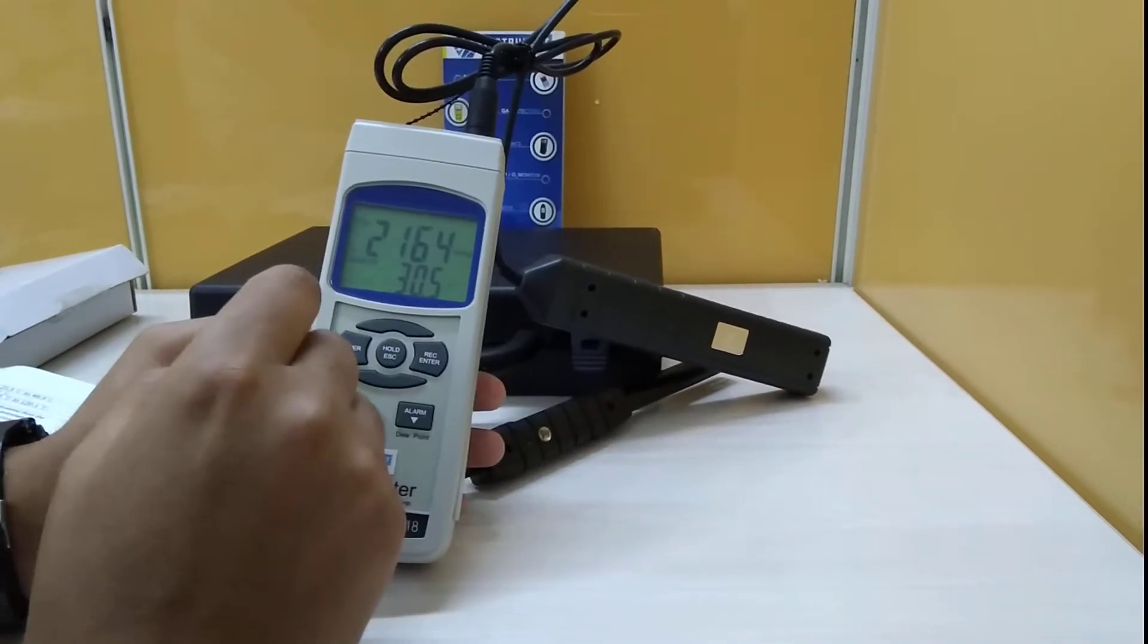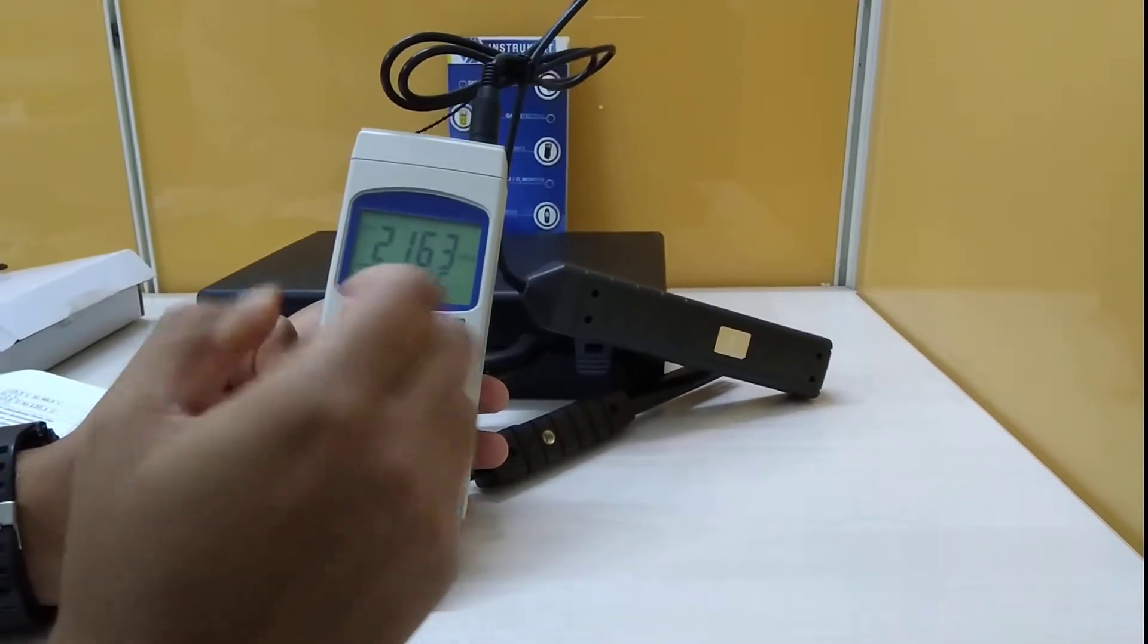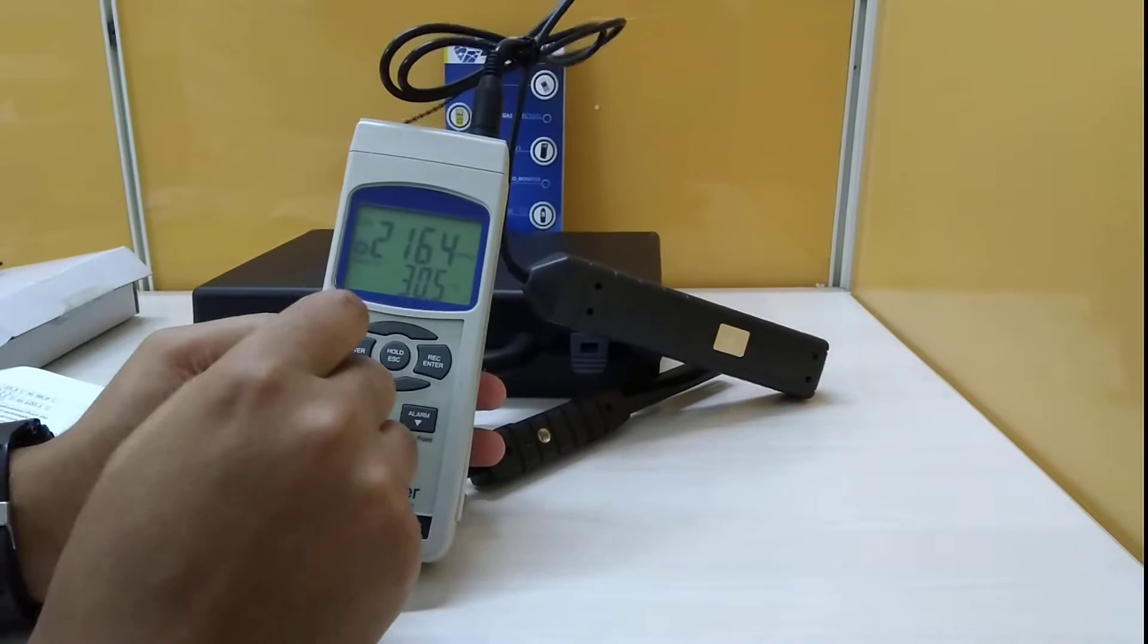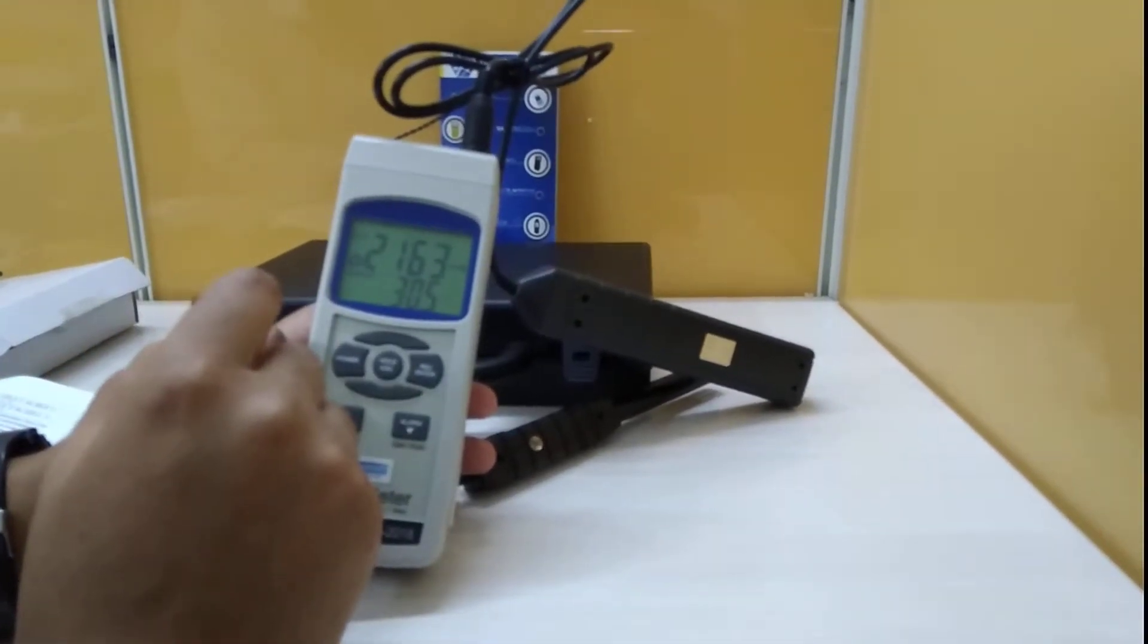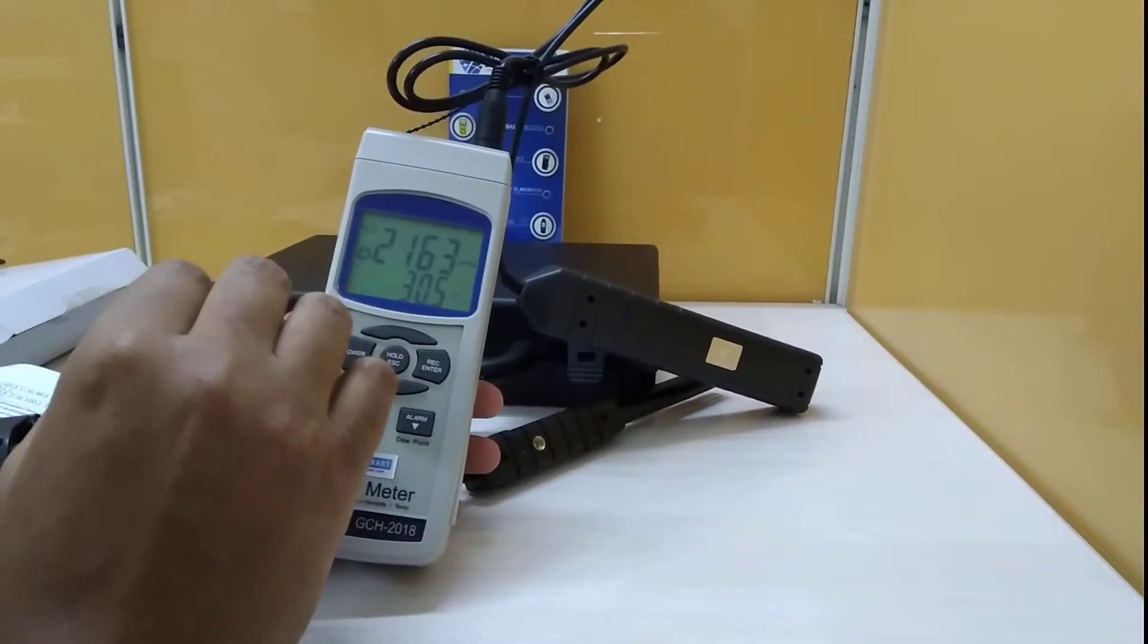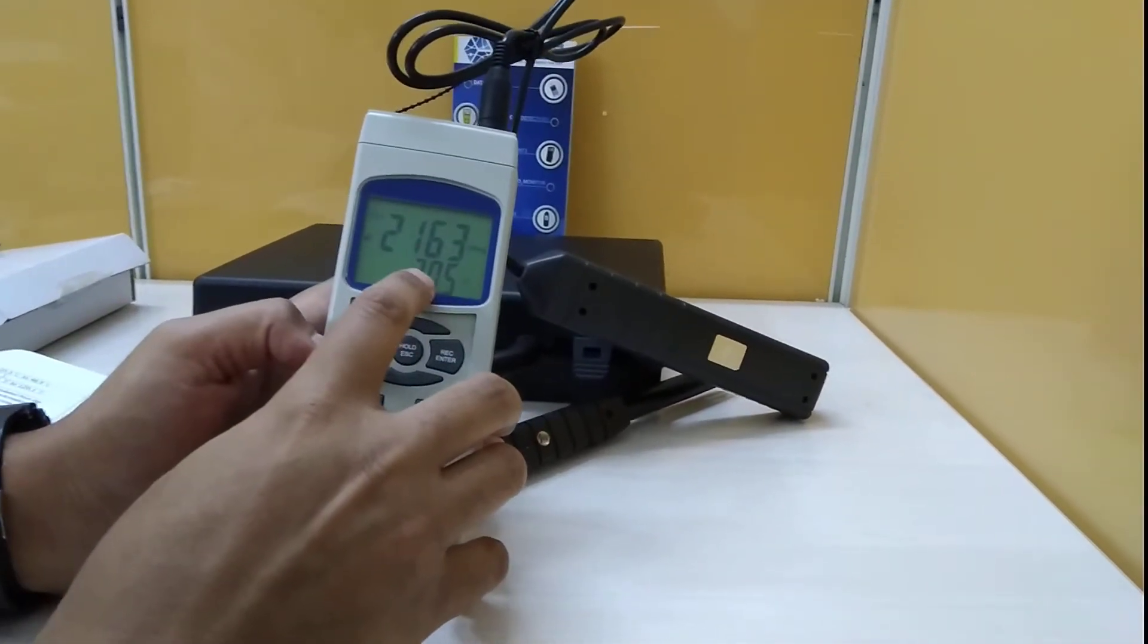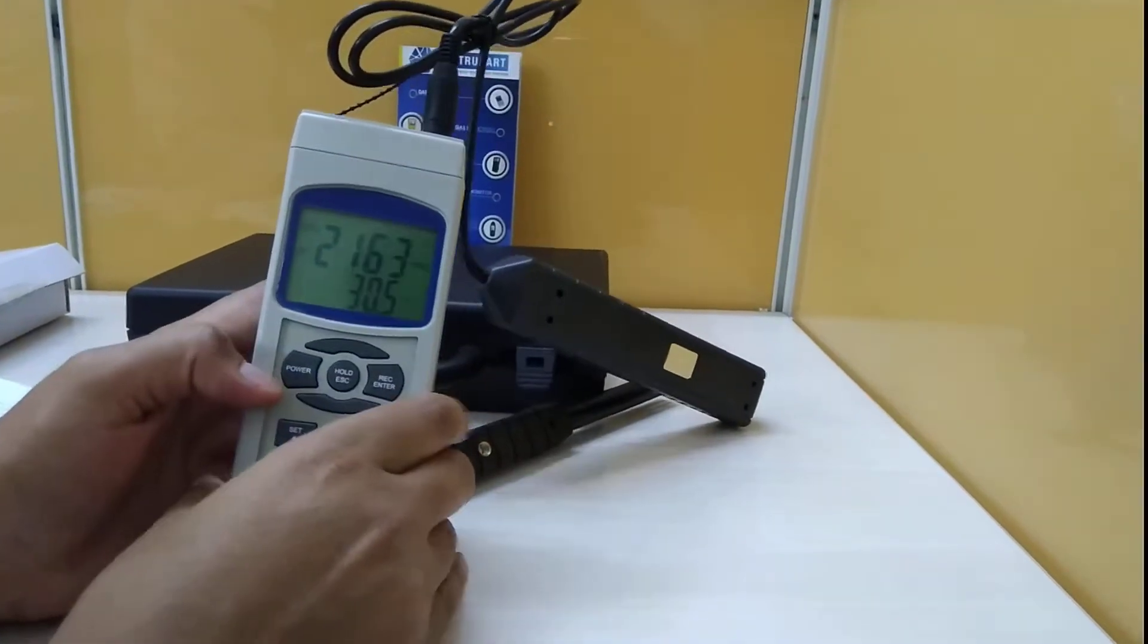The resolution is 1 PPM and accuracy is plus or minus 40 PPM when less than 1000 PPM. When the reading is 1000 to 3000 PPM, it's 5 percent of the reading, and if it's more than 3000, it's plus or minus 250 PPM. This will also display the temperature along with the PPM range as you can see in this big LCD screen.